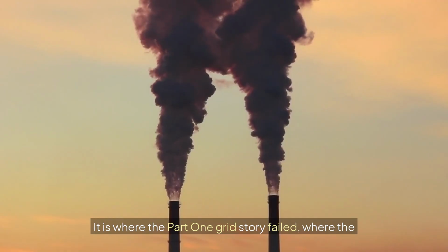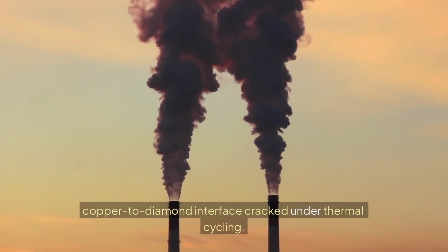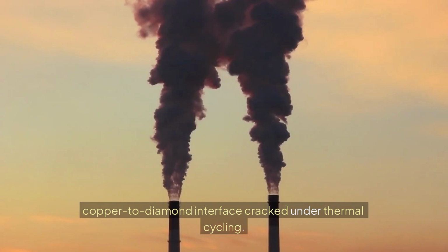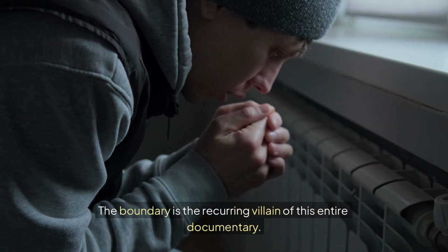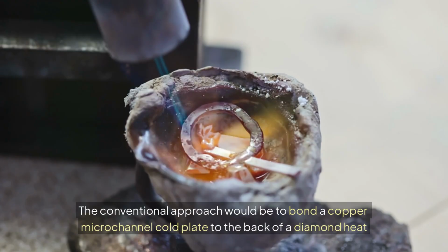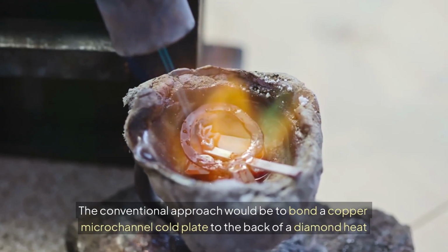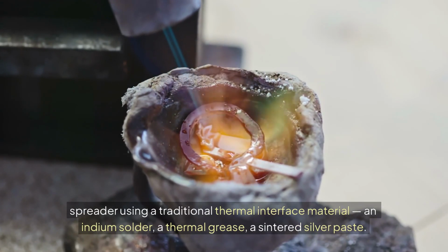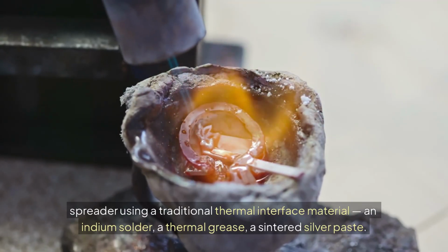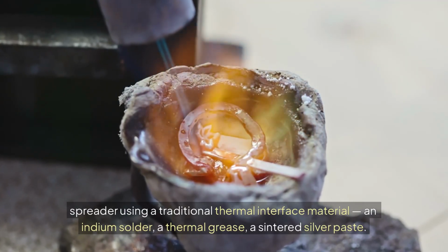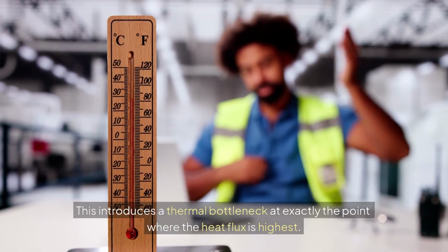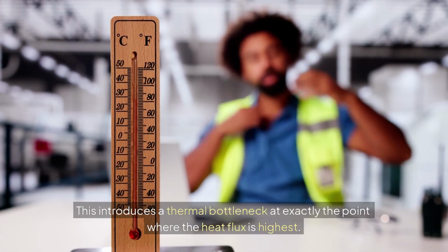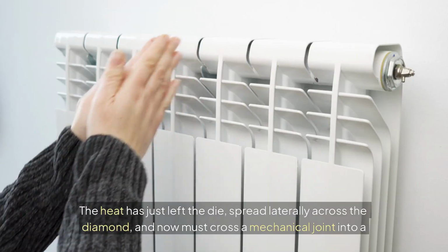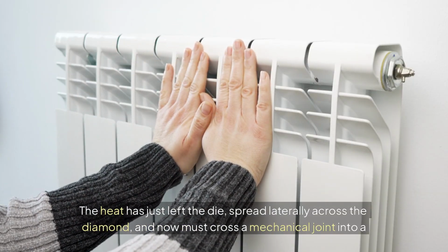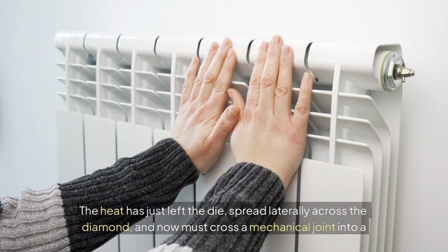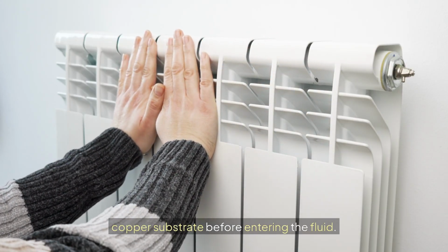It is where the Part 1 grid story failed, where the copper-to-diamond interface cracked under thermal cycling. The boundary is the recurring villain of this entire documentary. The conventional approach would be to bond a copper microchannel cold plate to the back of a diamond heat spreader using a traditional thermal interface material, an indium solder, a thermal grease, a sintered silver paste. This introduces a thermal bottleneck at exactly the point where the heat flux is highest. The heat has just left the die, spread laterally across the diamond, and now must cross a mechanical joint into a copper substrate before entering the fluid.